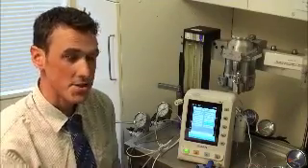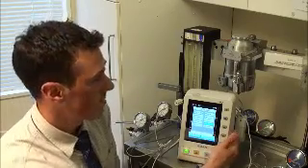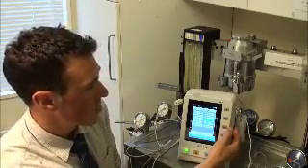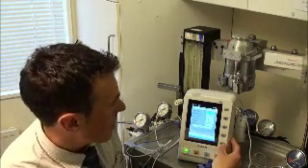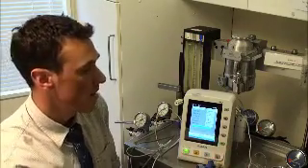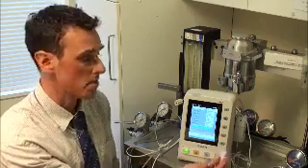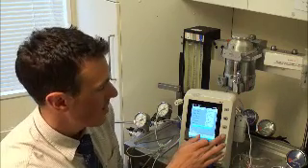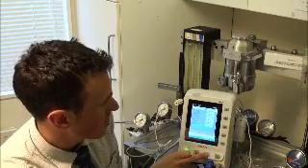If you've just attached a new adapter, you will need to zero it first. To do this, scroll to CO2 Setup and select. The last option on the menu is Zero Cal. Making sure that your adapter is nowhere near a source of carbon dioxide, select and switch on the monitoring.